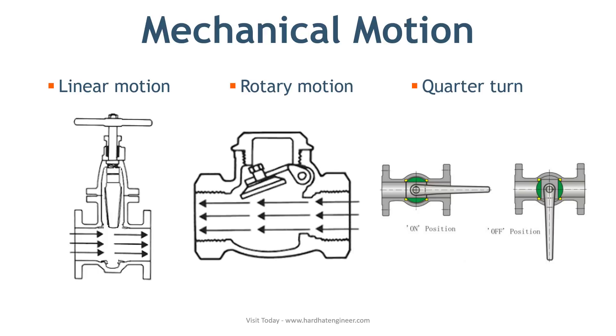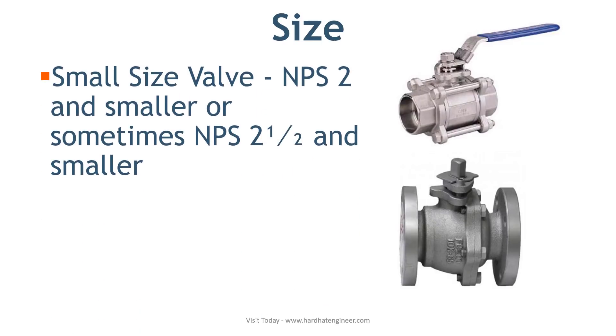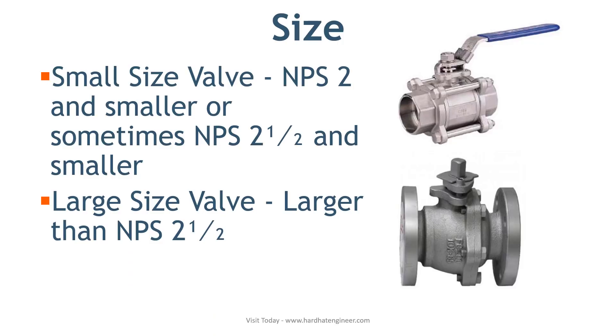Classification based on size. Valve size is defined by the nominal pipe size, which is equal to the size of the valve connecting end or flange end size. The valve size is not necessarily equal to the inside diameter of the valve — a 6-inch valve does not necessarily have a 6-inch opening. Based on size, valves are grouped as small size and large size. Normally, NPS 2 and smaller, or sometimes NPS 2.5 and smaller, are considered small size valves. This sizing classification can vary from company to company. Valves larger than NPS 2.5 inches are generally classified as large size valves.